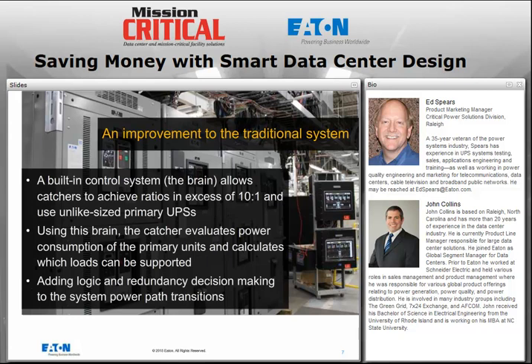That's exactly right. And just as an example, a large unloaded UPS with 0% load on its output can easily draw 10 to even 20,000 watts every hour that it's online. So you don't want to hamper your system efficiency by deploying a system in this type of situation. And if you can make the catcher system optimally sized, you can help with that type of thing.